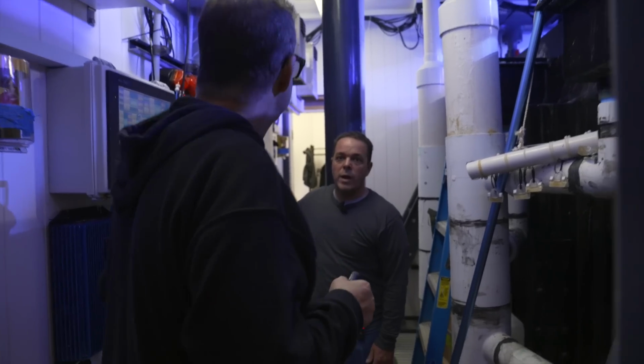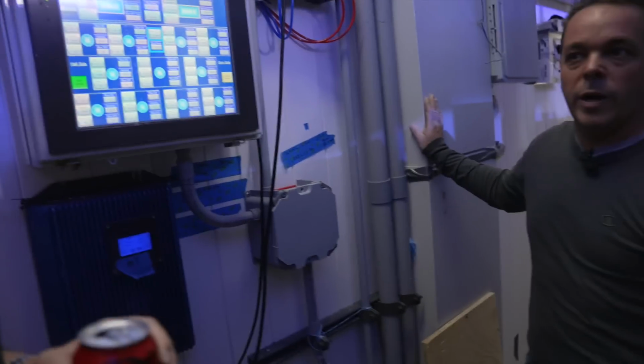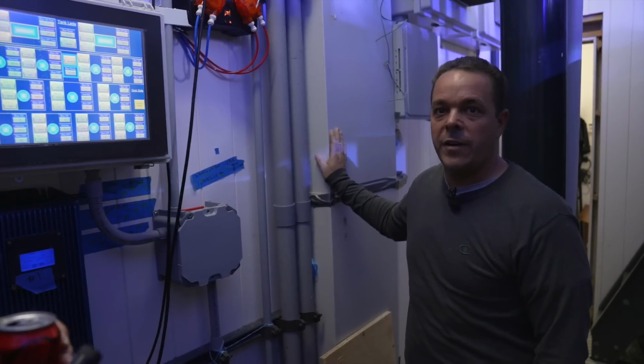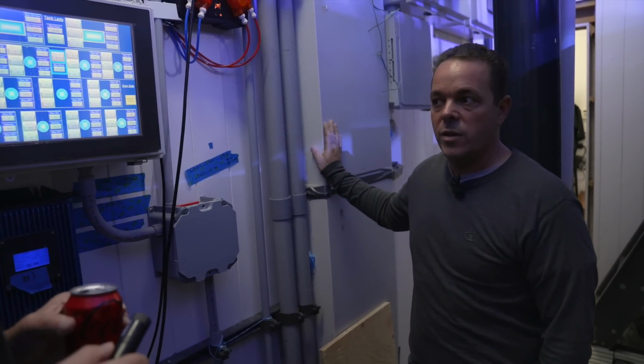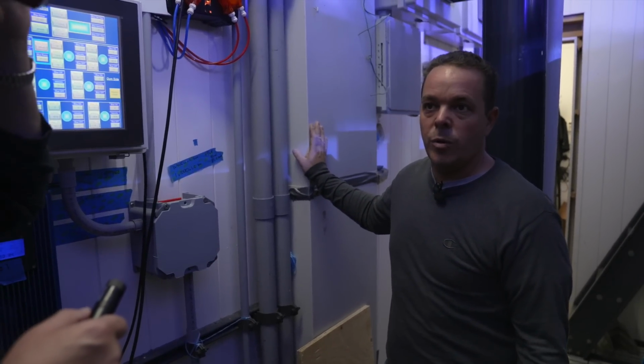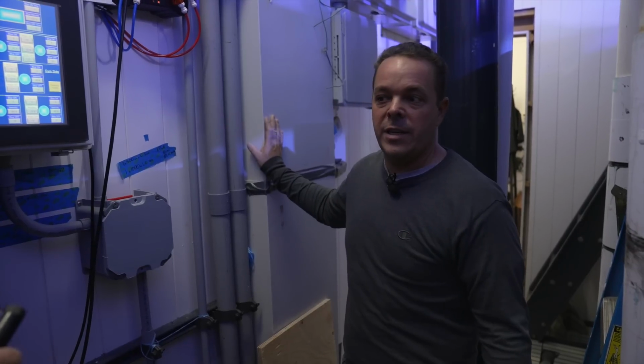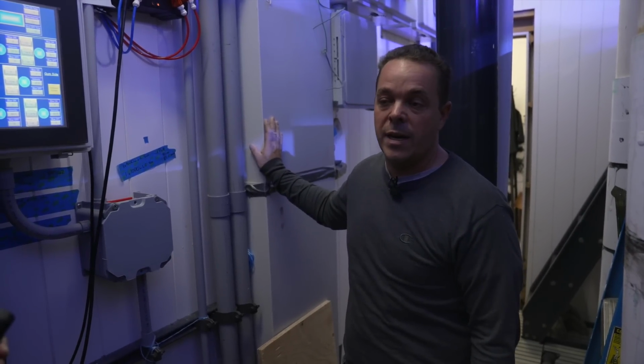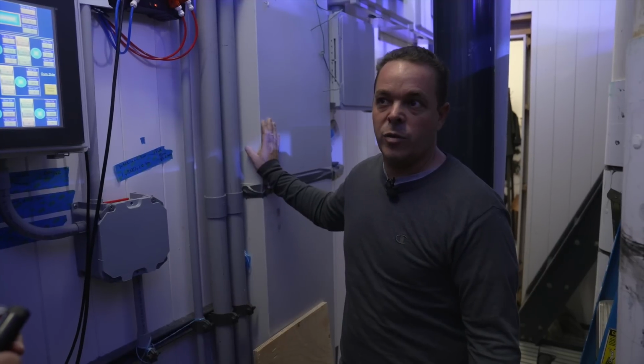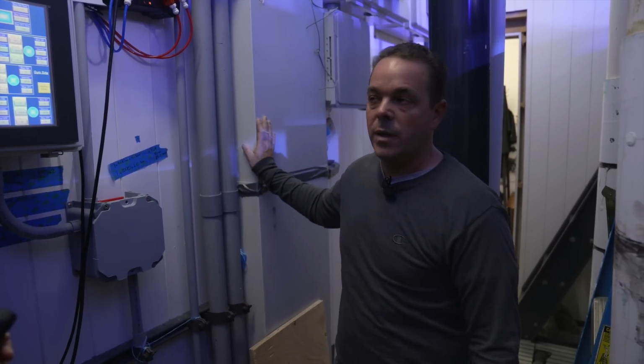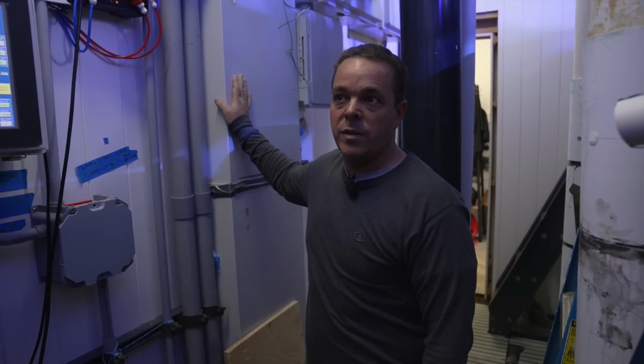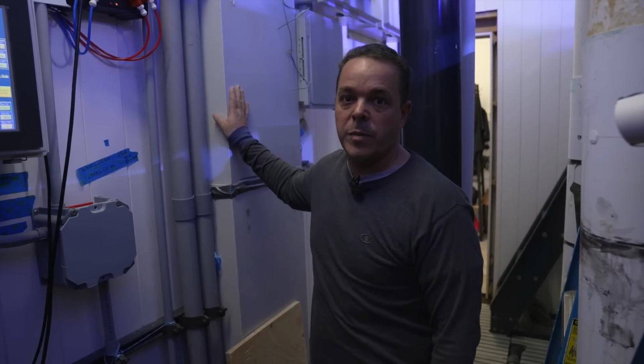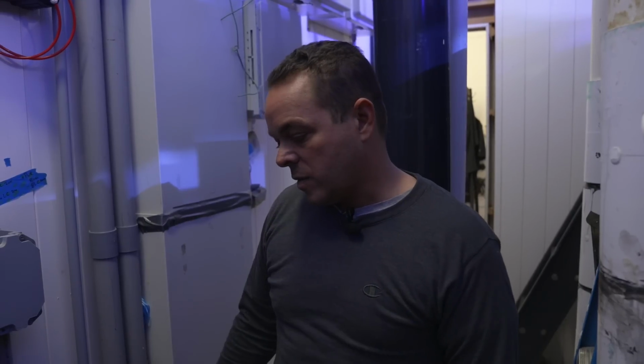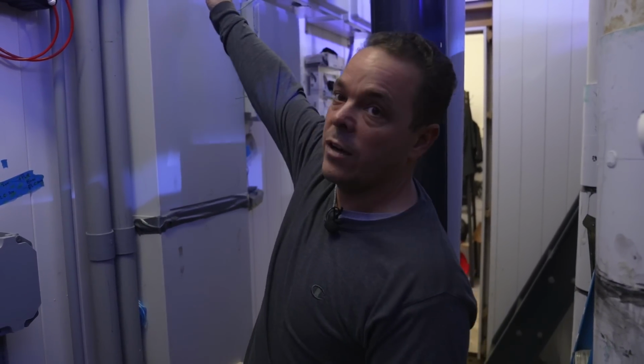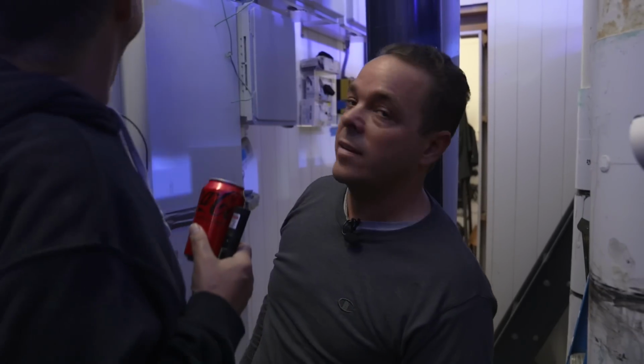So throughout multiple spots of the aquarium, we have these Dectron dehumidifying air conditioning units, which, depending on the temperature, will actually just dehumidify and then reheat the air, or if the temperature is too high, they'll dehumidify like an air conditioner normally does and just put the cold air back into the room. It's all run through these PVC coated ducts so that we don't have any rust from a regular metal ductwork. The supply to the unit is underneath this grate, and this is the return cut out high that blows cool air on top of the tank.